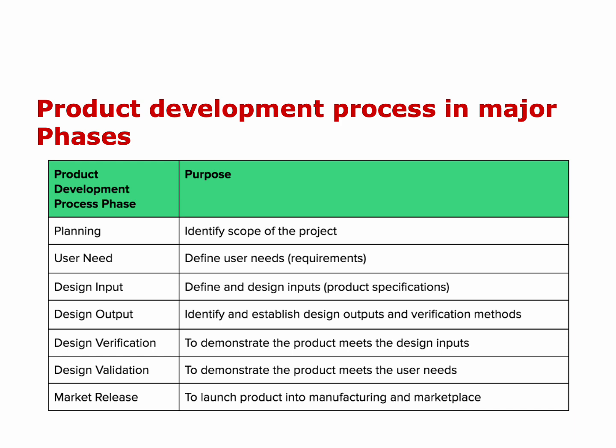Then we are going to look into the user needs. So the user is usually the patient, not always, maybe also a doctor who is going to use it on patients. And then here we are going to define the user needs. Here we talk about requirements. We need to have, for example, a device which is again mobile. It's not very heavy. It will have a battery. It doesn't need to be necessarily, for example, plugged in. It needs to have some software in it.